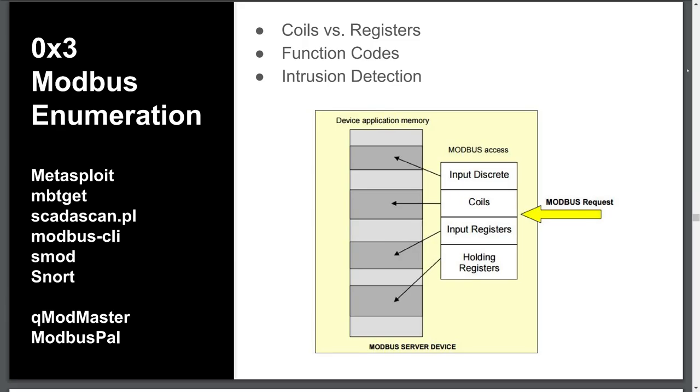The first set of addresses are for coils. Coils house a single bit, 1 or 0, meaning true or false. You may hear this referred to as bool or boolean. These block addresses are read-writable and can be modified by toggling the bit on or off, which makes them great for digital inputs and outputs.